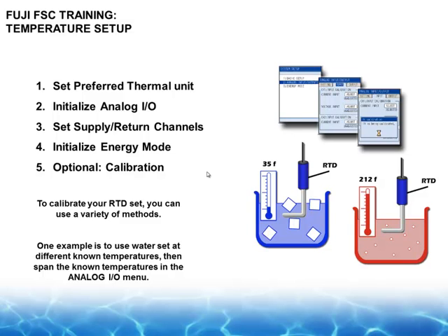If you have to use wetted RTDs, again, you have the ability. It's the 3-wire platinum input that we use, and then basically we just need a 4-20 milliamp input signal with a device should you need to do something like this.